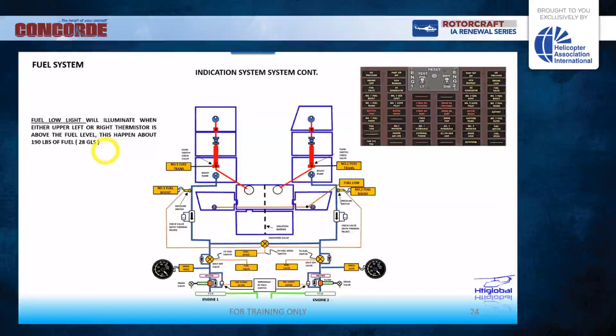Okay. Now, here comes the other one. I was mentioning to you only one thermistor is dry. Now, if you have both thermistors dry, meaning the fuel is below both thermistors, that is a logic where the system opens the valve. Remember, the switch or the interconnect is open in normal position. It's going to be closed, and the system is going to open the valve. Because this is done by the system and not by the pilot, the valve is going to open and the light is going to stay on. This is what we call a disagreement light, because the switch is in one position and the valve is in another. So what the pilot has to do is bring the switch into the open position, which is already done.